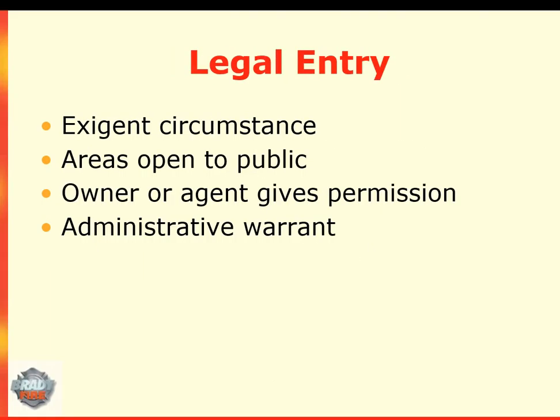1. An exigent circumstance including fire or other imminent hazard. Then warrantless entry is permitted to mitigate an emergency. 2. Areas that are open to the general public during public operating hours. 3. The owner or agent gives you permission to conduct the fire inspection, although permission can be revoked at any time, and once revoked you must leave the premises. And 4. The owner or agent refuses entry and you obtain an administrative search warrant from a court of competent jurisdiction.